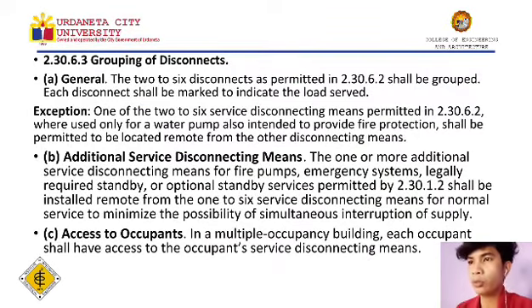And the next is 2.30.6.3, grouping of disconnects. First is general. The 2 to 6 disconnects as permitted in 2.30.6.2 shall be grouped. Each disconnect shall be marked to indicate the load served. The rules are that the 2 to 6 service disconnects must be grouped in the same location, either in a single enclosure or in separate enclosures located adjacent to each other. Obviously, the larger the service, the wider the grouping distance can become.